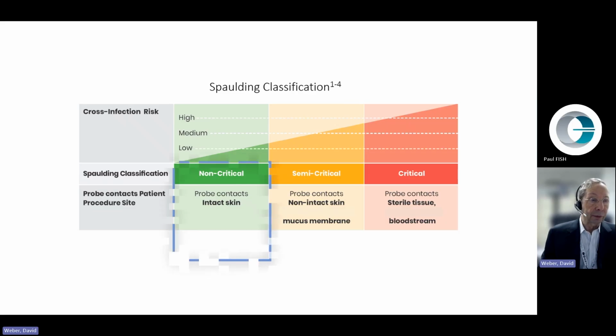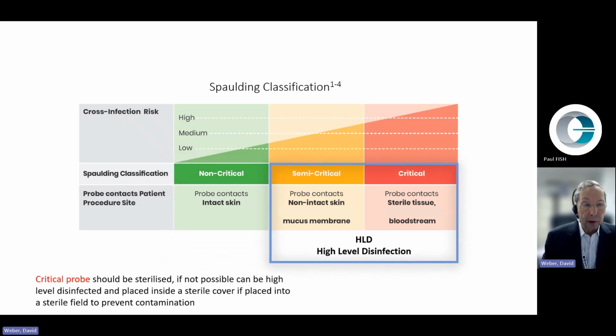And we have 3 different categories. We have non-critical under the Spaulding classification. This would be that the device, including a probe, contacts only intact skin, and the risk of cross-transmission is low. Then we have semi-critical. A probe contacts non-intact skin or a mucous membrane, and the risk of cross-infection is considered medium. Finally, we have critical. A probe contacts sterile tissue or the bloodstream, and the risk of cross-infection is high. Now, for semi-critical and critical items, we would either use sterilization, or if the device cannot be sterilized, we would use high-level disinfection.